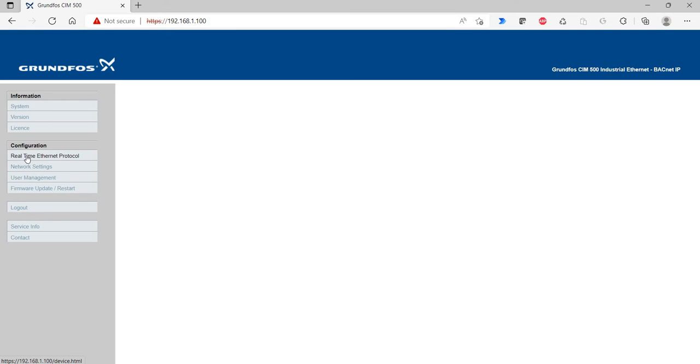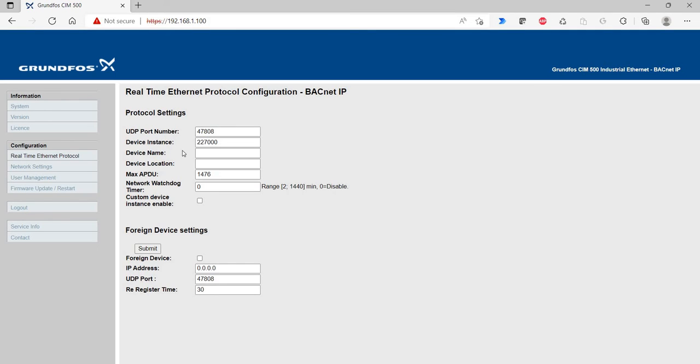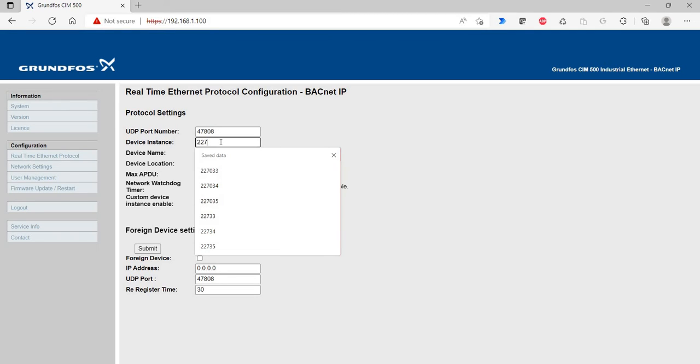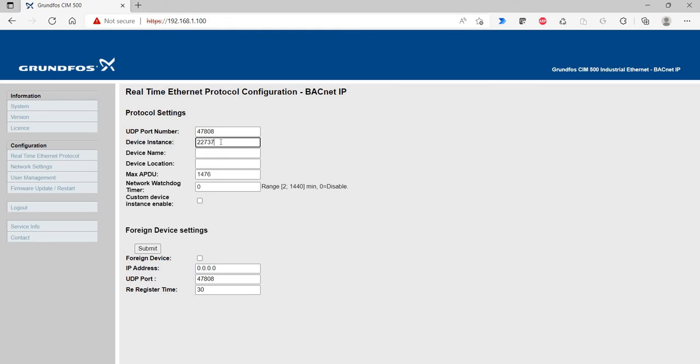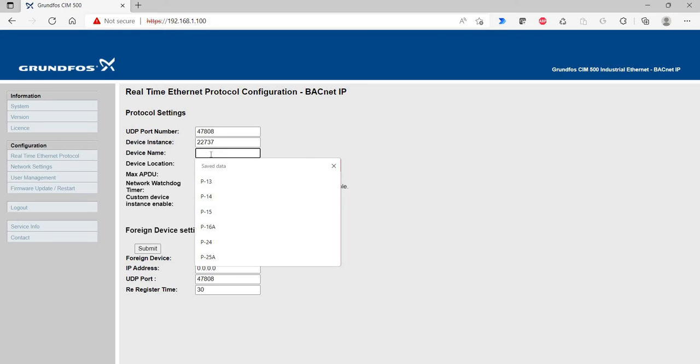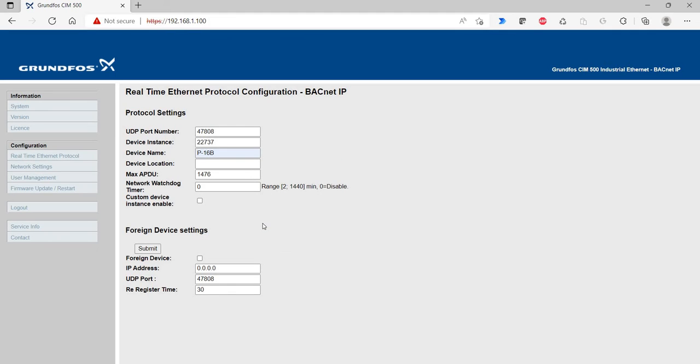And go to the BACnet protocol settings. So, I'm using five digits. You need to keep the 227 because that's Grundfos's prefix. I've been using five digits. It works fine. My device name is p16b. And I have to hit submit on this or it won't take those changes.